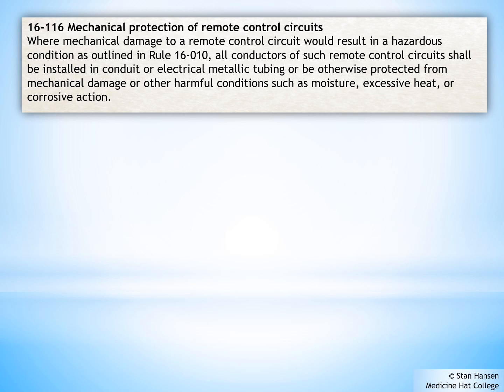Rule 16116 states that mechanical protection of remote controlled circuits must also be in place. It refers back to Rule 16-010, which states that any remote control circuits that operate safety devices are deemed to be Class 1 circuits. So any remote control circuits in accordance with that rule need to be protected from mechanical damage, moisture, and corrosion. The type of things that we're talking about are wiring for the high limit switches, exhaust interlocks, boiler low water cutoffs, or high pressure switches. All these are safety switches and they will need to be installed in either a conduit or a flex to provide that mechanical protection.